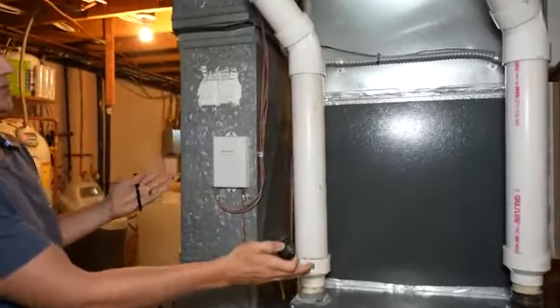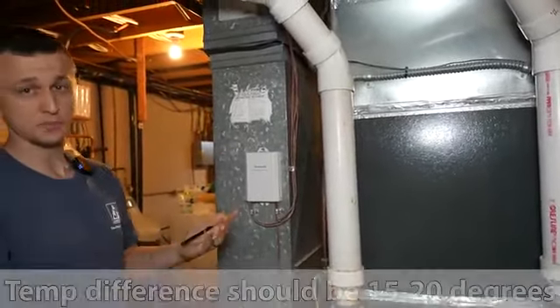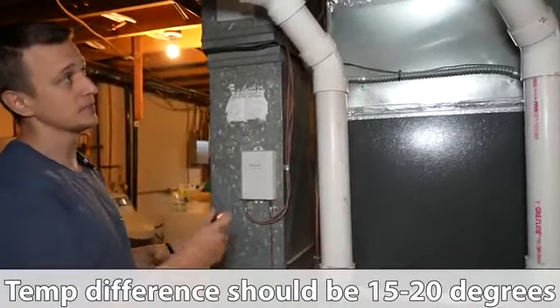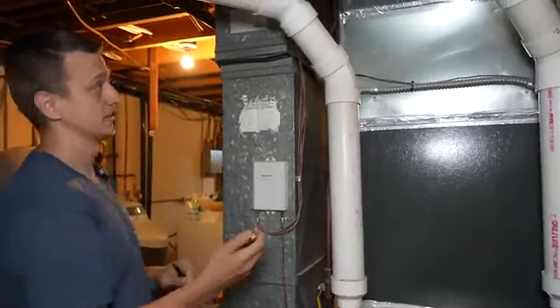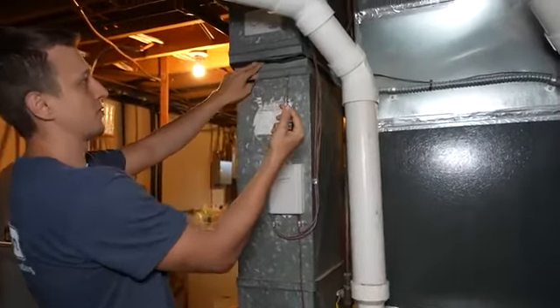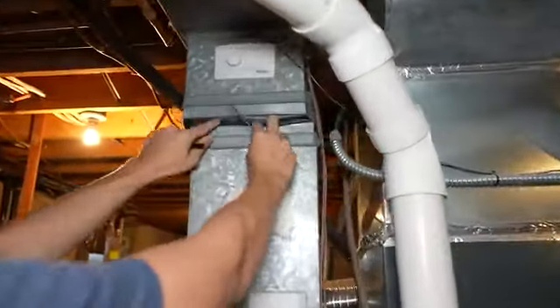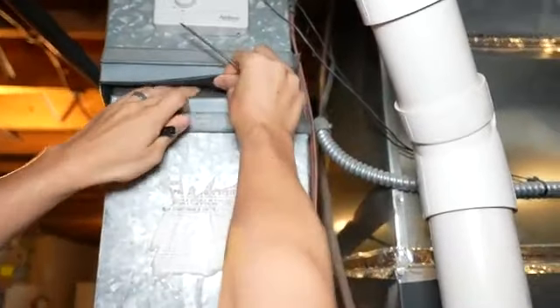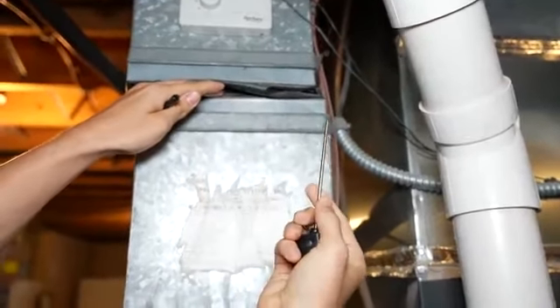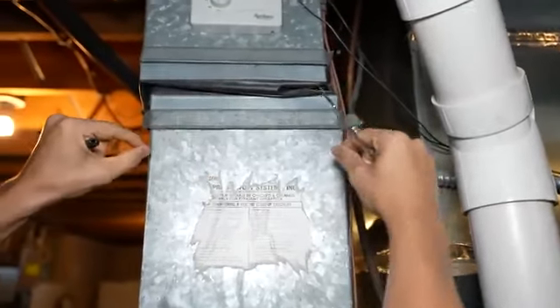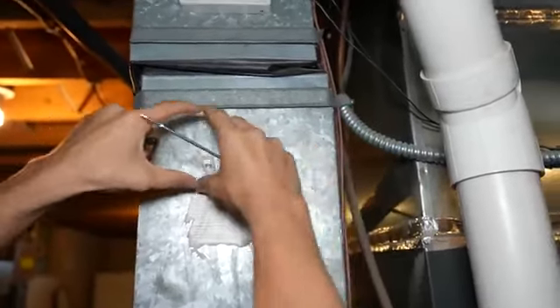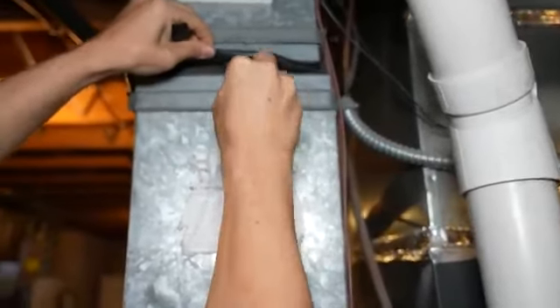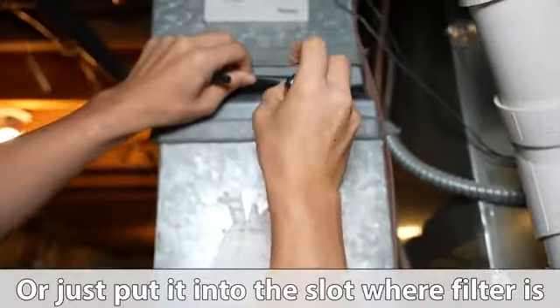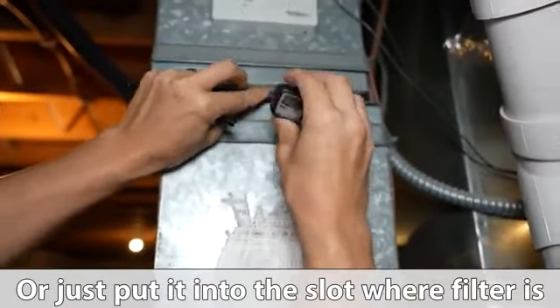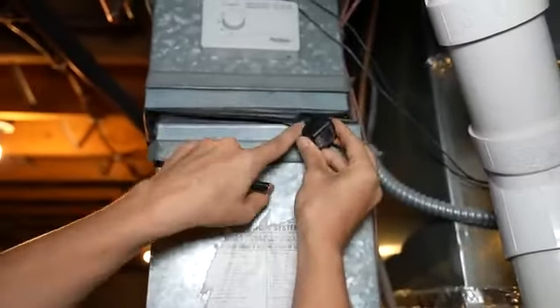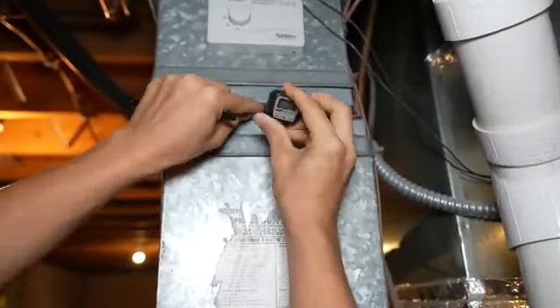So we want the temperature difference between the two, which, on a normally working air conditioner, should be somewhere between 15 to 20 degrees. So let's try it. You can insert your thermometer into one of these canvases, these flexible things. And if you're worried about making a hole in it, don't be. I mean, if you think about your vents, they're a gigantic hole in the duct. That's what a vent is. So you making a tiny hole inside of this rubber thing, that's not gonna do anything. So don't worry about that too much. I mean, you don't wanna make the hole too big, but just a little size hole like this, that's fine.